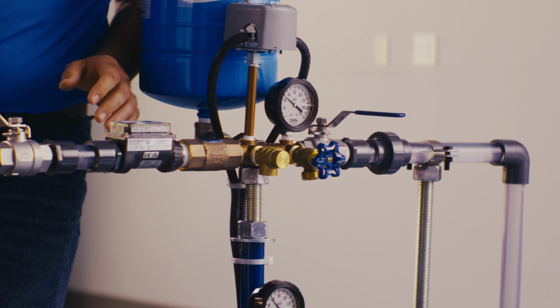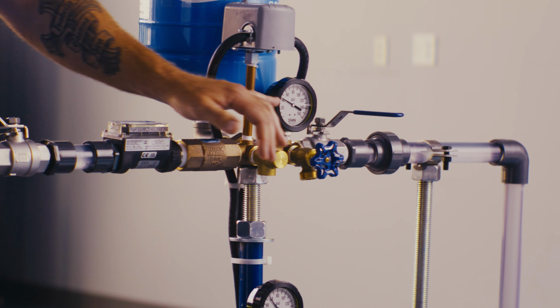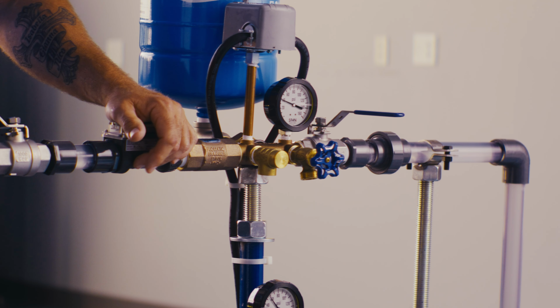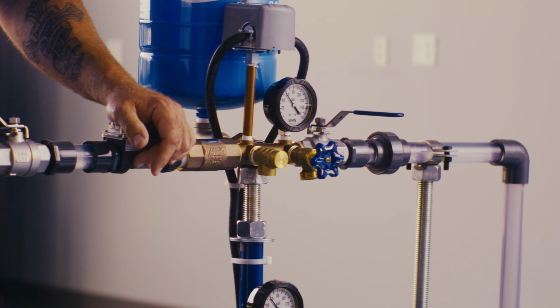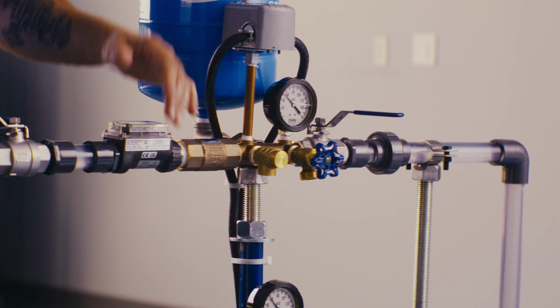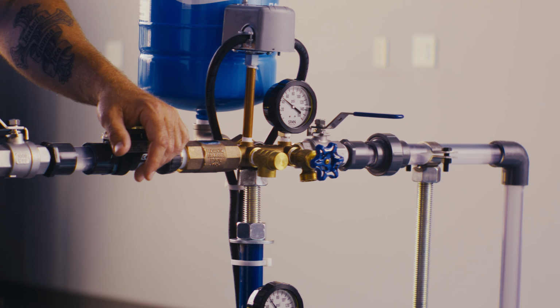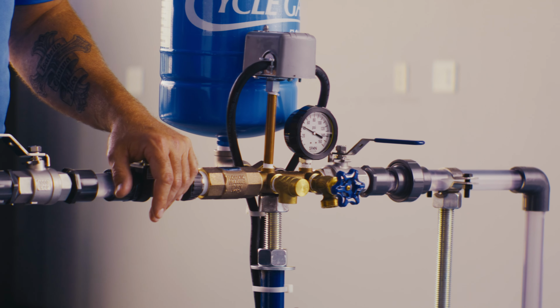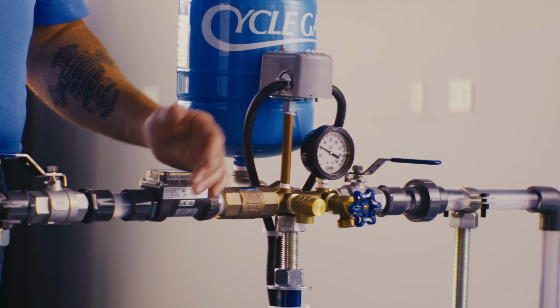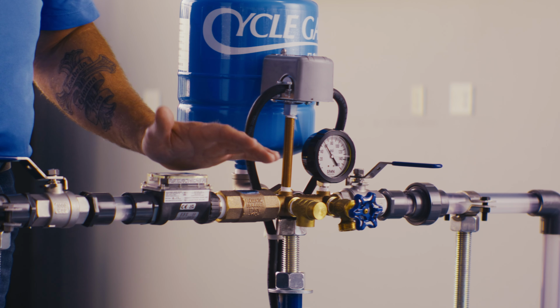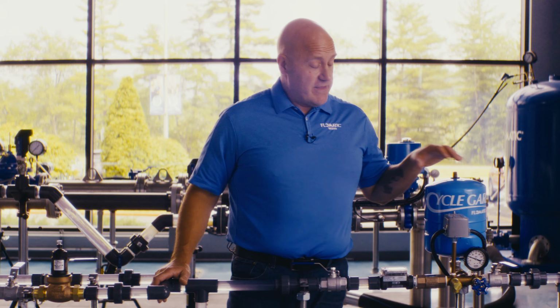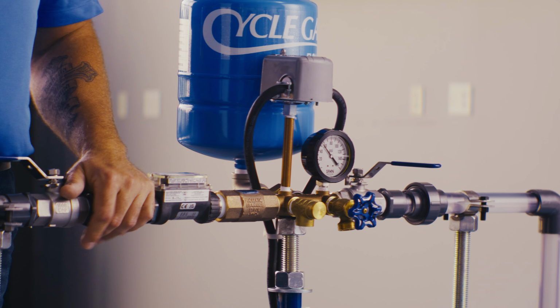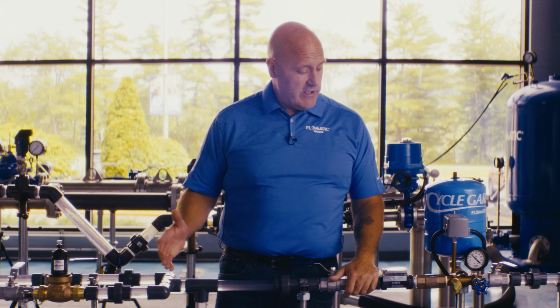So pressure's dropping. Once that pressure gauge hits about 40, the switch is going to engage, turn the pump on. Pump is now running. It hit 60, it shut off. So it's going to drop to 40, kick back on again. I don't know, maybe a 10-second cycle time, something like that. With the rapid starting and stopping of the pump with this small of a tank, that is bad for our pump. That is bad for our motor. So we want to eliminate that.